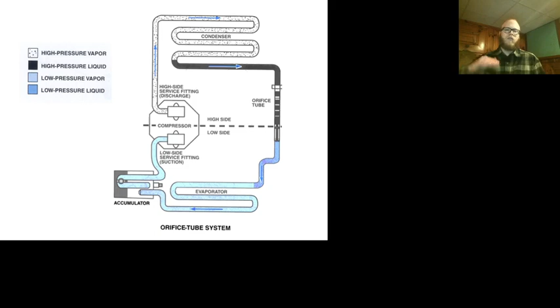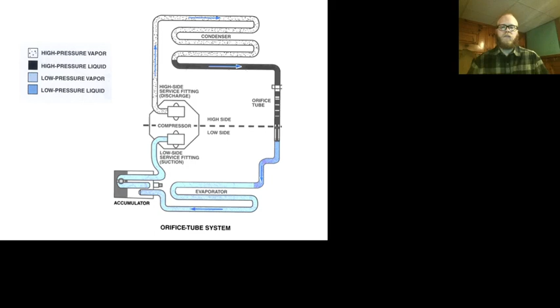Oh, it's too cold, or we're going to get liquid into our compressor. Shut it off. That way we have time for the refrigerant to absorb more heat energy, and also we're starting to slow down the cycle. Even with the system turned off, because I've built up all this pressure here, it takes a while for it to equalize and stop flowing, but turning the compressor off is going to have a huge effect on the pressures and also the amount of flow that occurs.